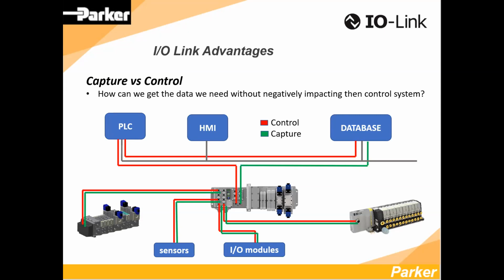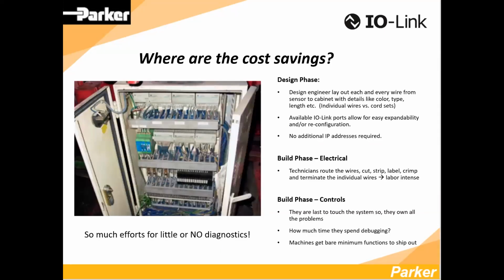But the capture of the data - if you notice, that's the green line as opposed to the red - the collection of those sensors goes through the master. It does not go through the PLC, and goes right back up to the database. Many different forms of the database - I kind of just summarized it like that. But basically it's data collection on up off the plant floor, bypassing the PLC and therefore not impacting the PLC.